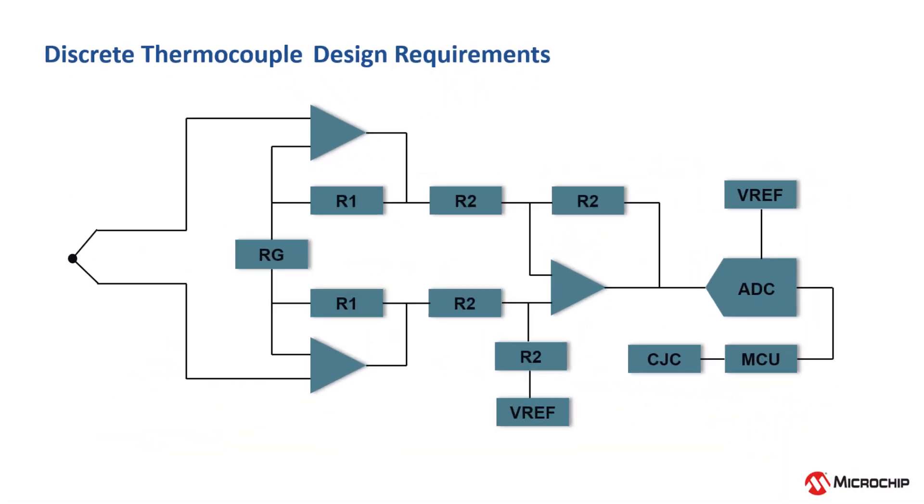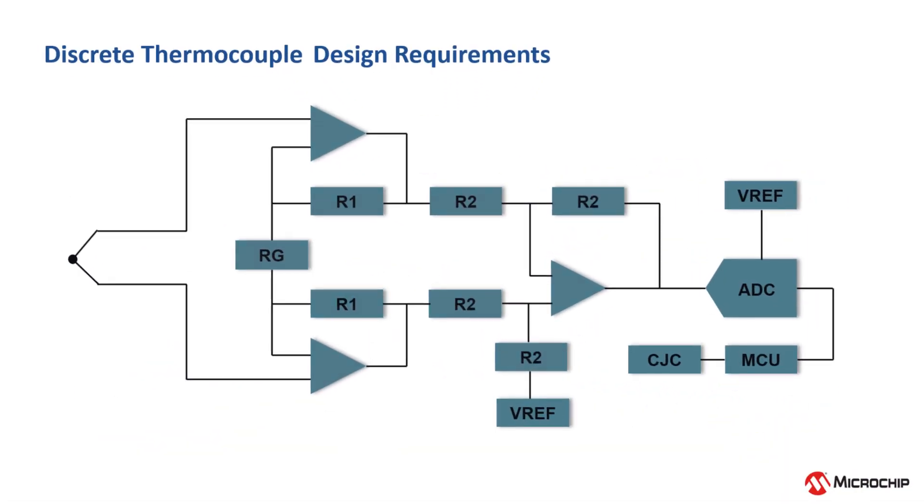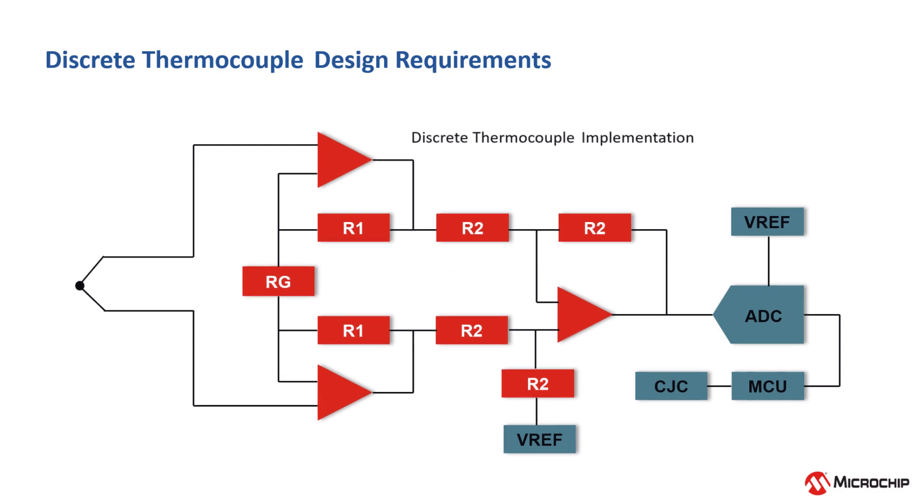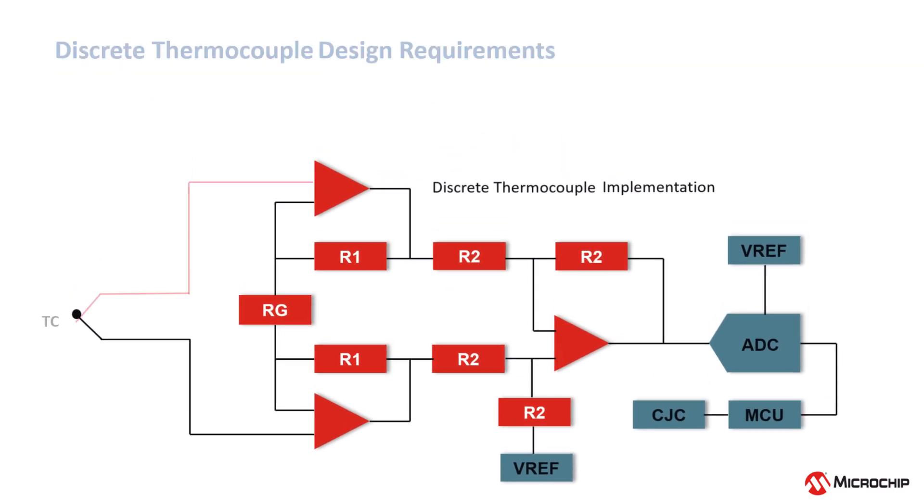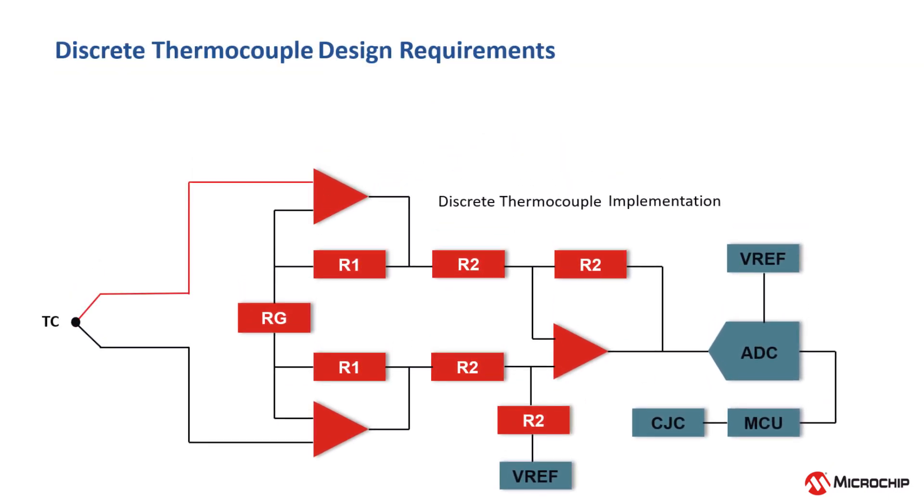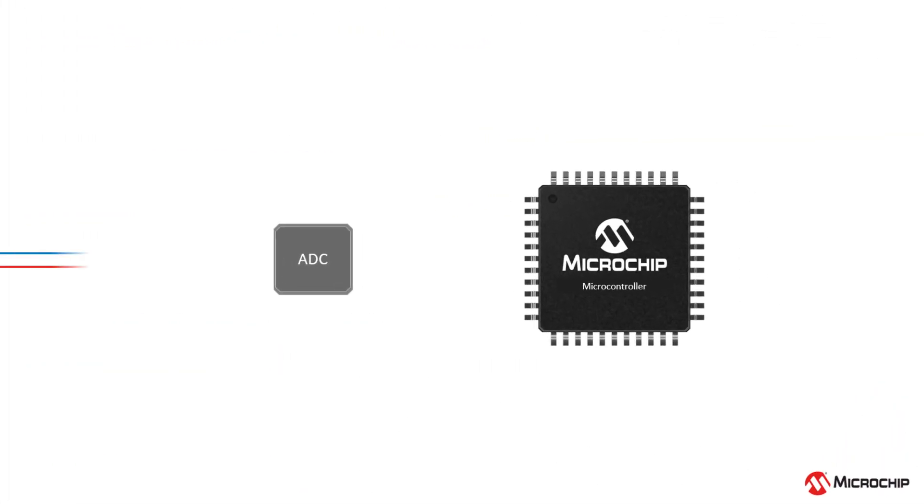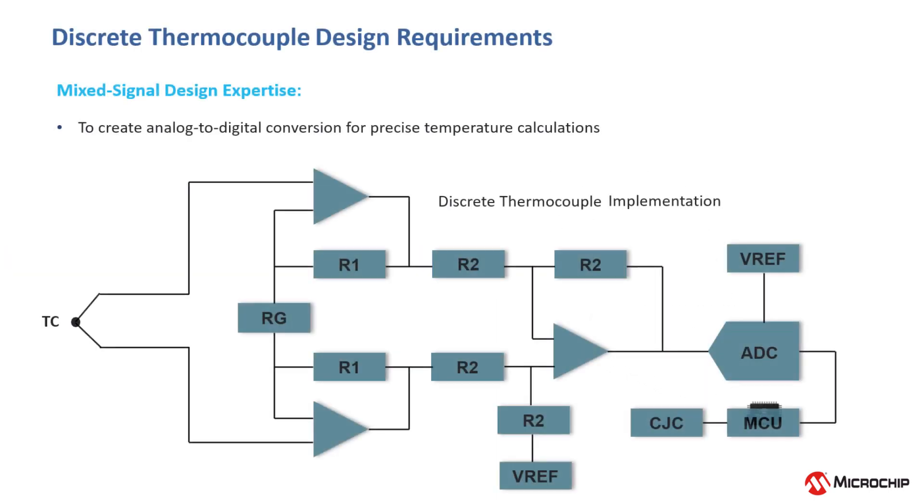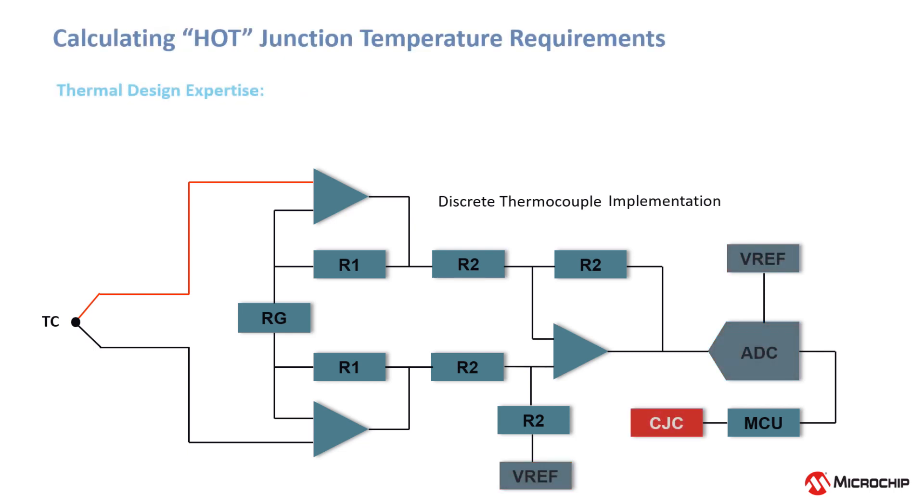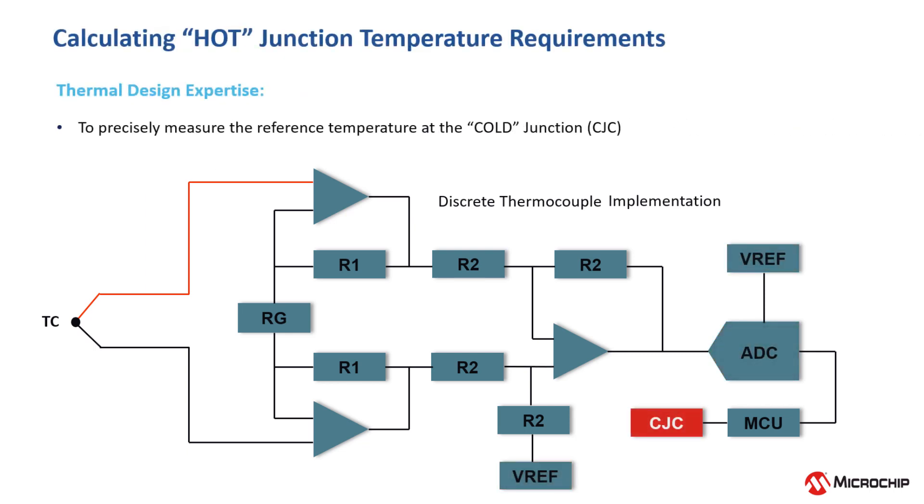For the discrete solution, this requires many areas of design expertise. First, precision instrumentation circuitry is needed to accurately measure the microvolt level changes in the voltage at the cold junction. The voltage measured at the cold junction must then be converted from the analog domain to the digital domain for processing. In order to convert the measured voltage into the hot junction temperature, one must accurately measure the temperature at the cold junction.